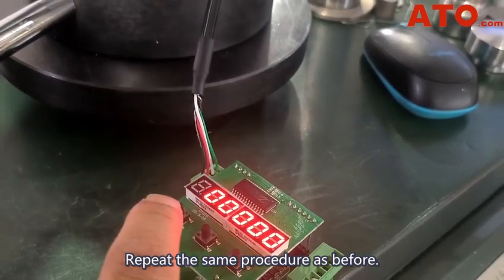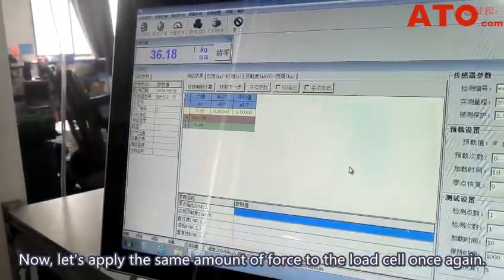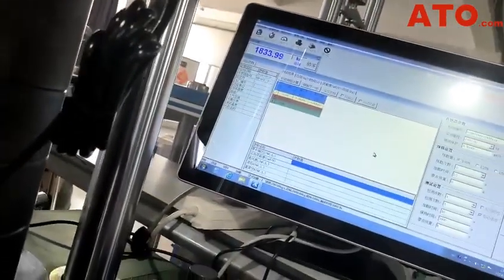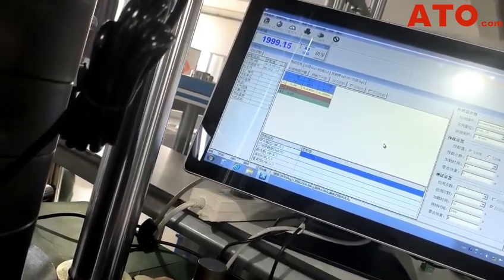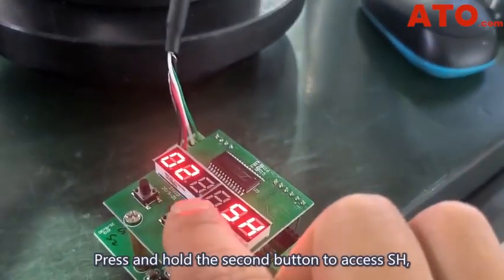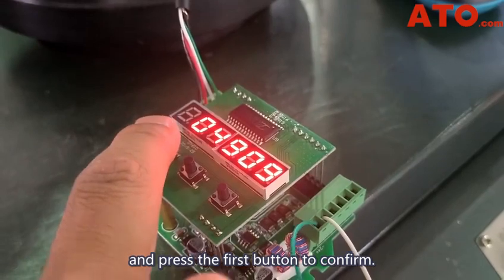Repeat the same procedure as before, ensuring all values are set to zero. Now let's apply the same amount of force to the load cell once again. Press and hold the second button to access SH. Verify the modified value of 4909, and press the first button to confirm.